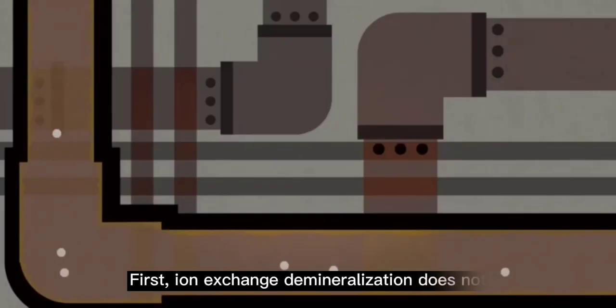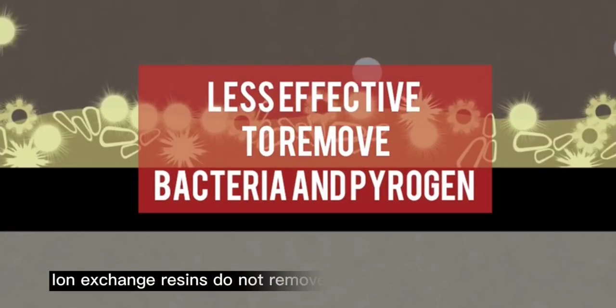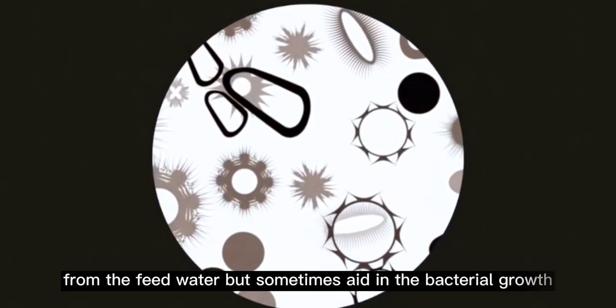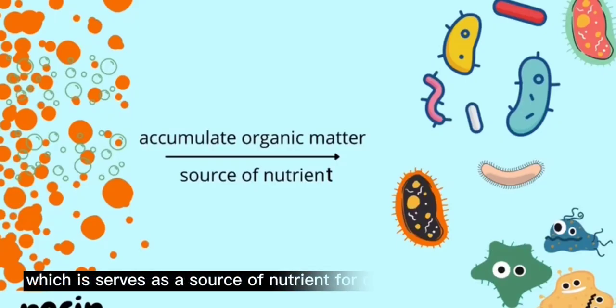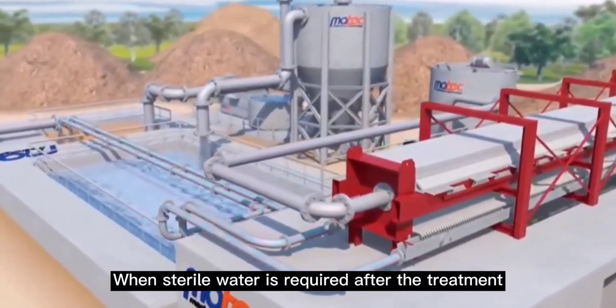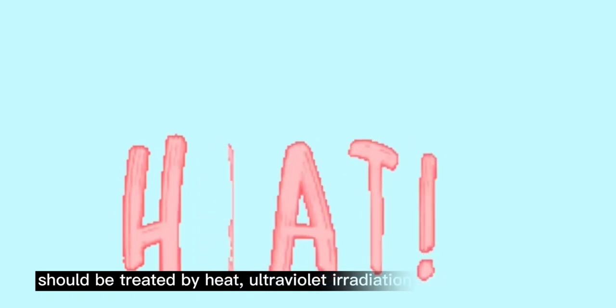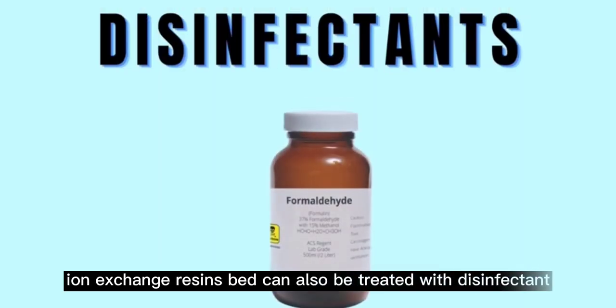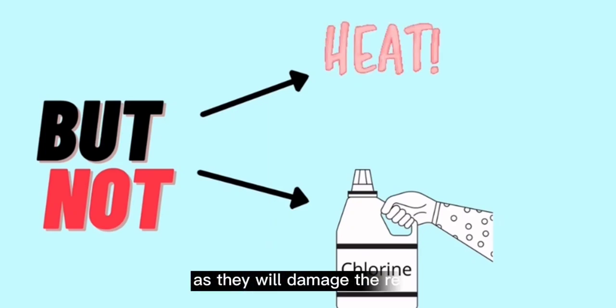Ion exchange demineralization also has its own disadvantages. First, it does not effectively remove bacteria or pyrogen. Ion exchange resins do not remove microorganisms like bacteria from the feed water but sometimes aid in the bacteria's growth. The resin beds may accumulate organic matter, which serves as a source of nutrients for continued growth of bacteria. When sterile water is required after treatment, the demineralized water should be treated by heat, ultraviolet irradiation, or very fine filtration. Ion exchange resin beds can also be treated with disinfectants such as formaldehyde but not with heat or chlorine, as they will damage the resin.